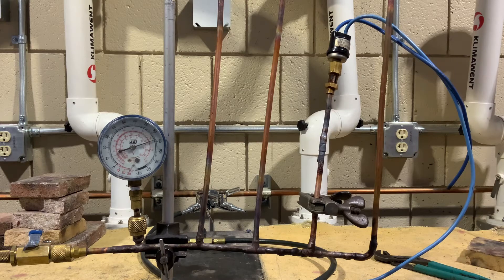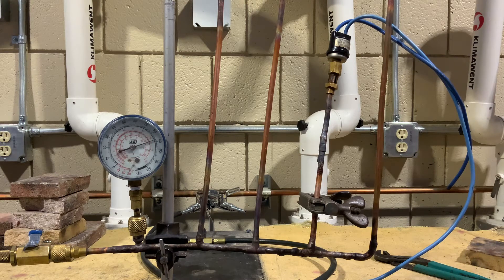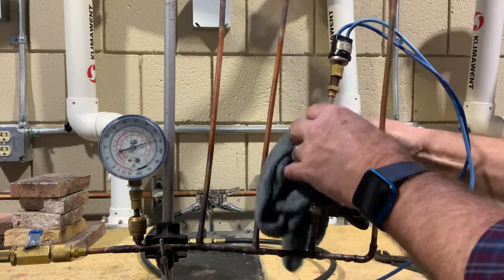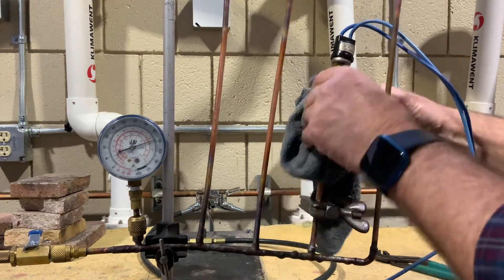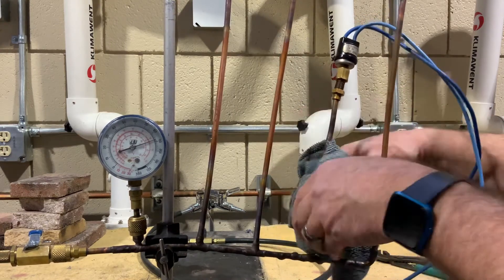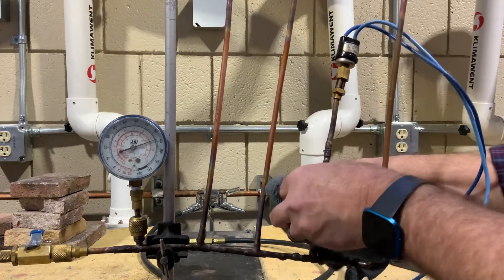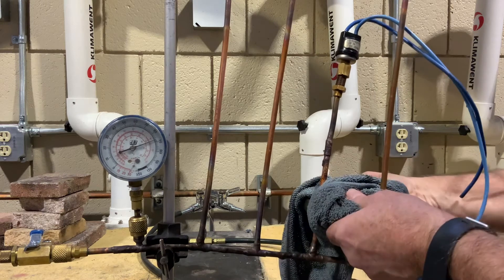So essentially, I changed out that pressure control without taking any refrigerant out of it. Now cool this off nice. Don't want any burn fingers while we're doing this. Even our pinch-off tool here will get a little bit warm. So we want to kind of cool that off too.